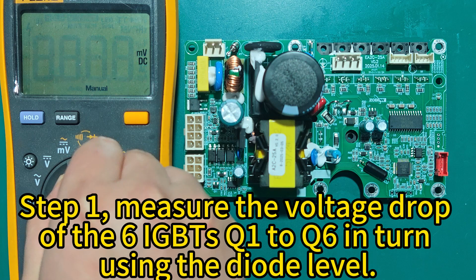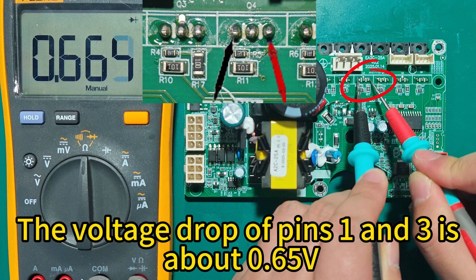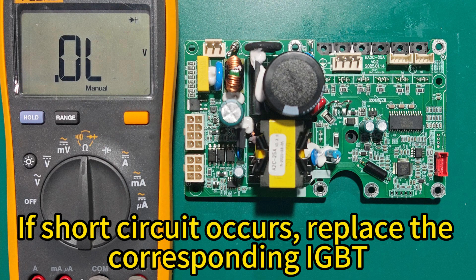Step 1. Measure the voltage drop of the 6 IGBTs, Q1 to Q6, in turn using the diode setting. The voltage drop of pins 1 and 3 is about 0.65 volts. The voltage drop of pins 2 and 3 is about 0.45 volts. If a short circuit occurs, replace the corresponding IGBT.